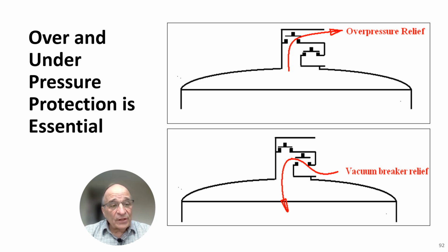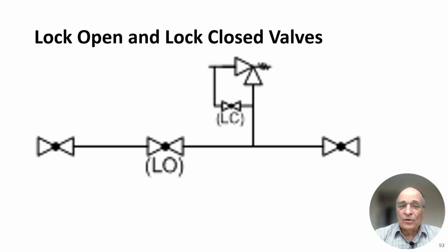Over and under pressure protection is essential for all tanks, especially large tanks. If you look at here, we're showing an under protection or vacuum breaker protection, and we've spoken about that already. And here we're showing an overpressure relief valve. Earlier, we've mentioned the need for having TESV, that's thermal expansion relief valves or safety valves. TESV is thermal expansion safety valves. Now, here's a thermal expansion safety valve.